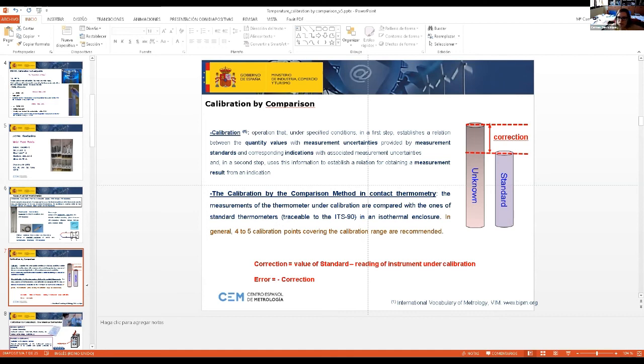In calibration by comparison, we want to compare the response of an instrument under calibration to the response of a standard at the same temperature. We define the correction of the instrument under calibration as the value of the standard minus the reading of the instrument under calibration. Please consider that the error is the same as the correction, but with the minus sign between them. This is important. It's the same amount, but the error is minus the correction.